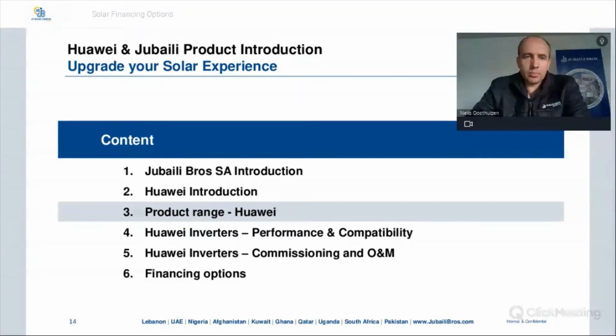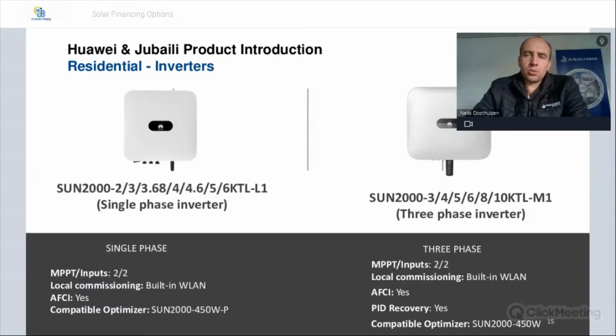Okay, moving on, we've got the product range from Huawei. I'm just quickly going to run through the product range. We do have specific webinars for each range of inverters or for a specific topic. So if you need more information, feel free to ask, but also have a look out for the dedicated webinars on that specific segment that you are interested in. On the residential inverters, we've got 2 ranges available. Please note at the end of each range, there's either a denomination L1 or M1. The L1 is specifically the single phase inverters, and the M1 is the 3-phase inverters.